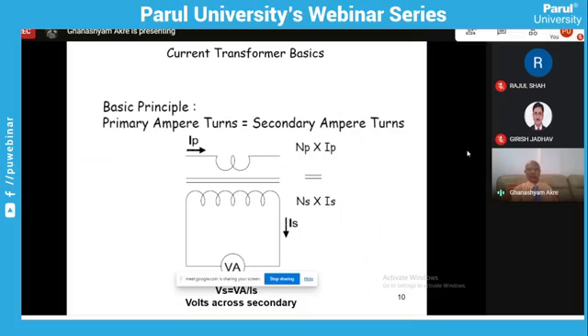Now here, this is the important principle of the transformer. Here you see that primary is shown as NP multiplied by IP. That means primary ampere turns. So the total primary ampere turns is to be balanced by the secondary. Secondary is shown as NS into IS. So depending upon NP and NS, you can have secondary currents. For example, if it is 100 by 1 ampere and I have a primary of 1 turn, then the secondary will have 100 turns, so that both these currents will go according to our design, that is 100 by 1 ampere.